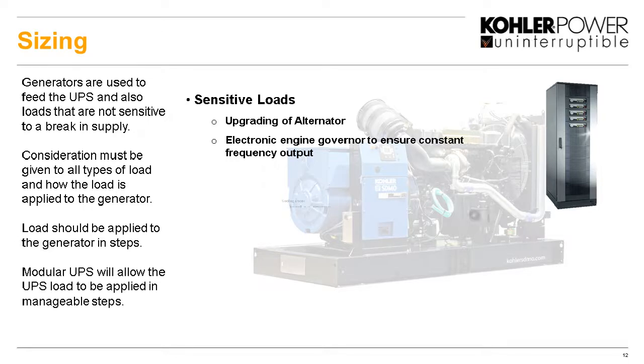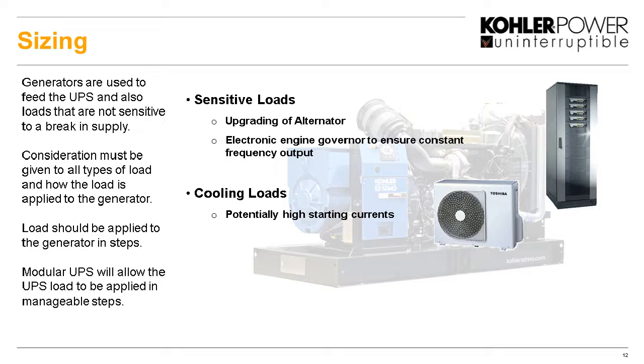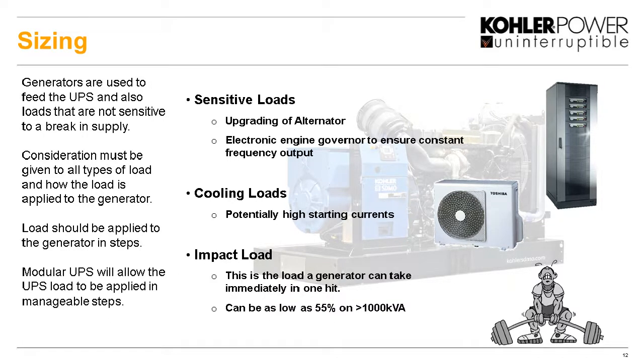So we also have to consider loads, like cooling loads, that potentially have very high starting currents. Now, like many things, there'll be a limitation to the inrush that we can have on the generator, as you would on any supply. So we have to be very careful of what that is when we're putting it onto the generator. So that impact load, it's the capability of the engine to maintain the output voltage and frequency depending on the load that is applied in one step.